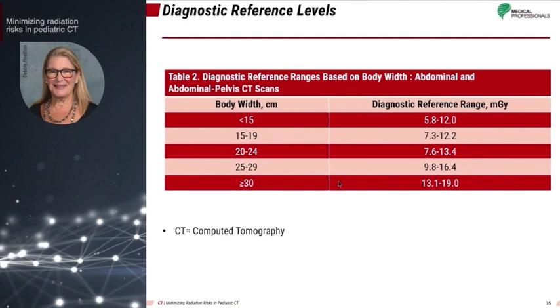DRR takes into account the subjective image quality of the examination and provides an estimated minimum dose to the patient, below which accurate interpretation of an image may be hard, and a higher estimated dose above which the patient dose may be above what's necessary.